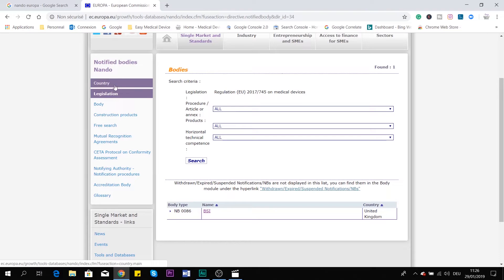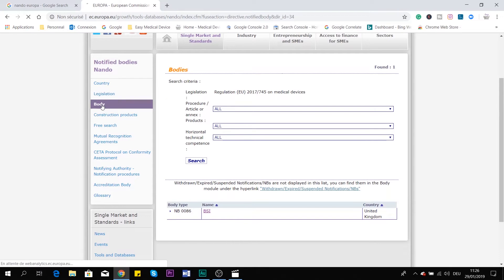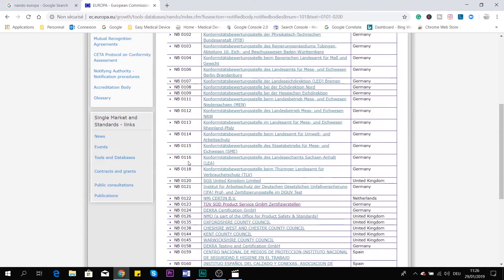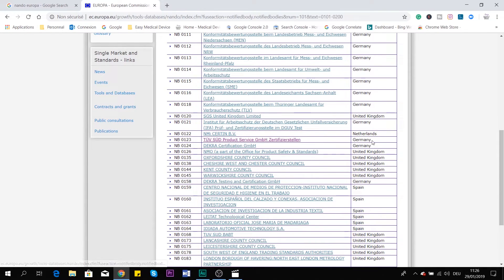So we have covered country and legislation. Now let's go to body. This is interesting because if you have a product and you don't know its notified body, but the product has a CE mark with a number behind it, you can use that number to find who the notified body is. For example, number 0123 is TÜV SÜD in Germany. You can see here which notified bodies are linked with that number.